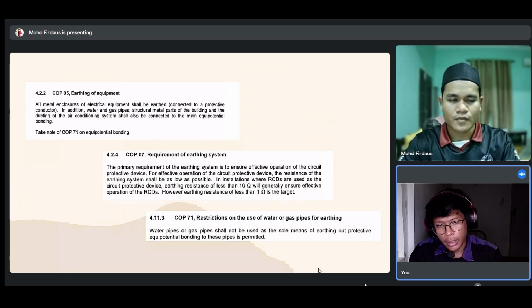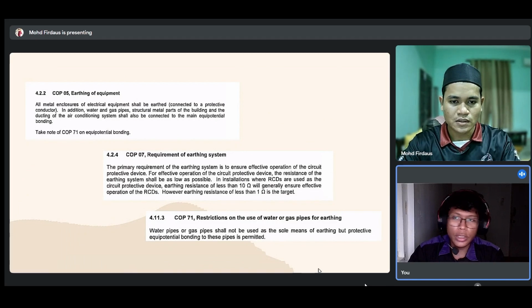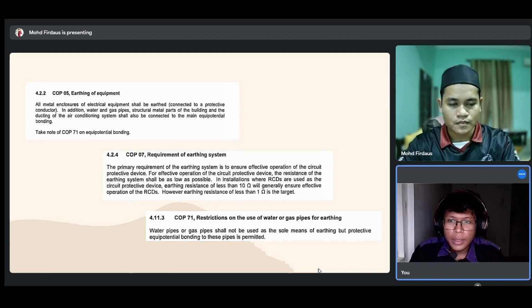From the question or topic, we can relate it to Code of Practice 05, on earthing of equipment, which states that all metal enclosures of electrical equipment should be earthed, meaning connected to a protective conductor. We can also relate it to COP07, requirements of the earthing system. As mentioned, the primary requirement of the earthing system is to ensure effective operation of the circuit protective device, and for this, the resistance of the earthing system should be as low as possible.